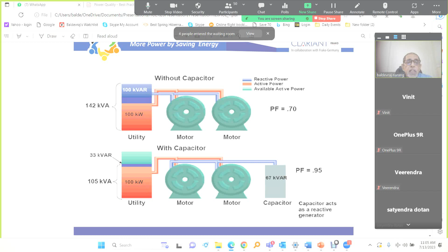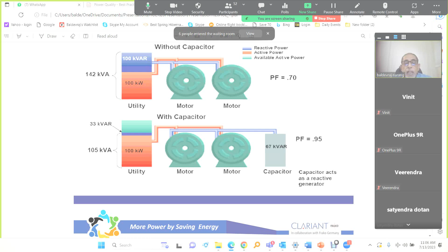And now suppose we put a power factor capacitor at the local location and improve the power factor to 0.95, and we are putting about 67 kVAr locally. We need to import now the remaining 33 kVAr from the grid, and the sanction, the demand also comes down from 142 to 105 kVA. And these days the target is to get a unity power factor instead of 0.95, so that we don't import anything and we have the optimum billing.